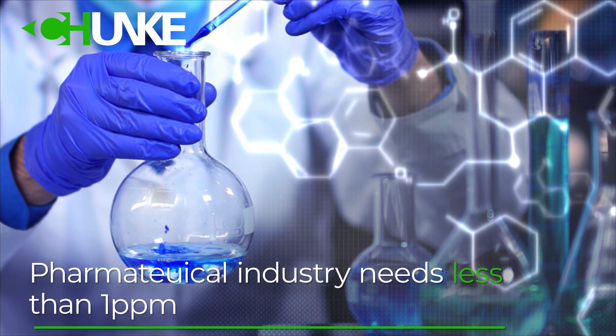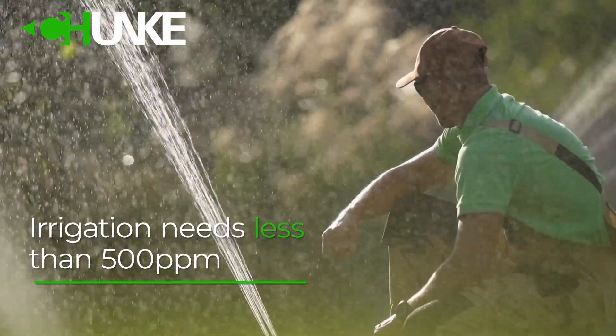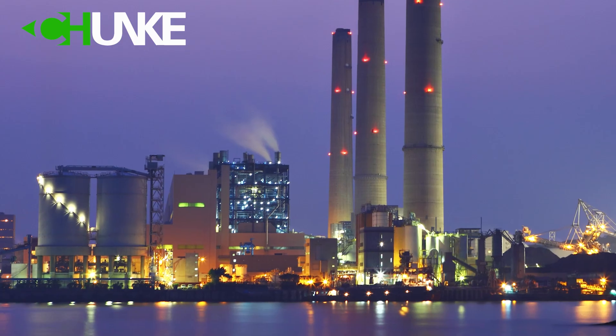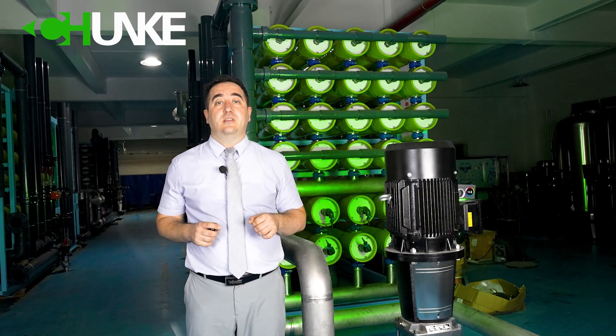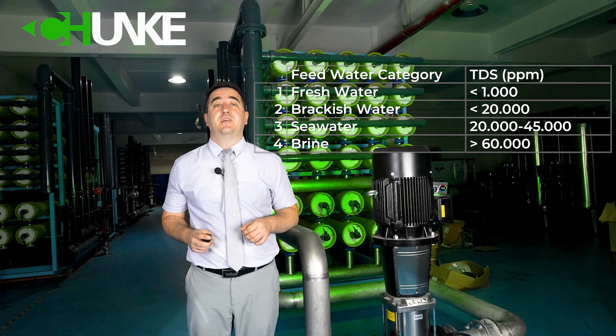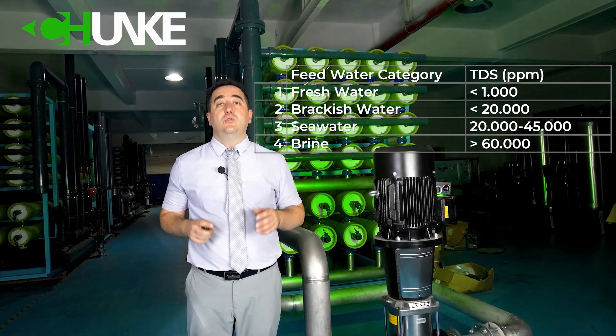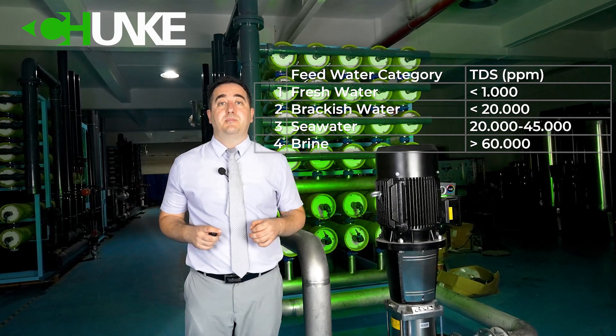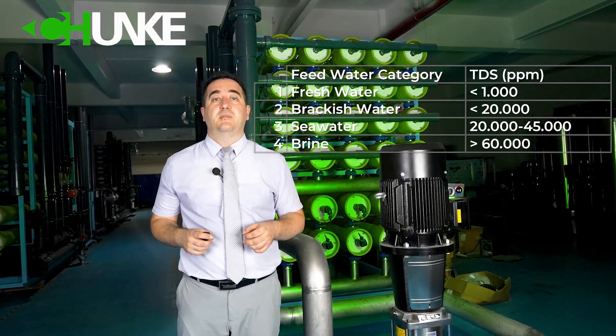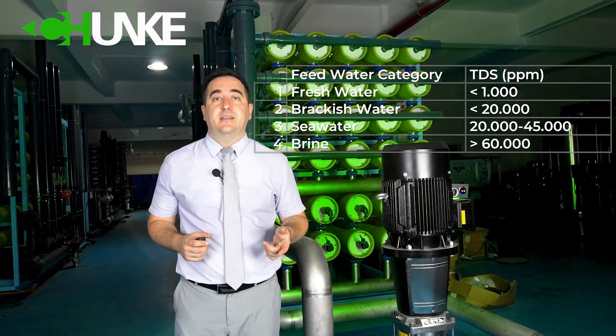Every industry has different demands — for example, the pharmaceutical industry needs water less than 1 ppm, irrigation needs less than 500 ppm, and power plants need less than 2 ppm. If you are not sure which TDS level is suitable for your process, don't worry — our technical team will help you. The second table categorizes water by source. Our sample test report shows a TDS level of 3580 ppm, which means it is brackish water. If TDS is higher than 2000 ppm, your system needs higher pressure, a bigger pump, special membranes, and other technical improvements. Therefore, TDS is a very important parameter for both you and us to design a correct system.